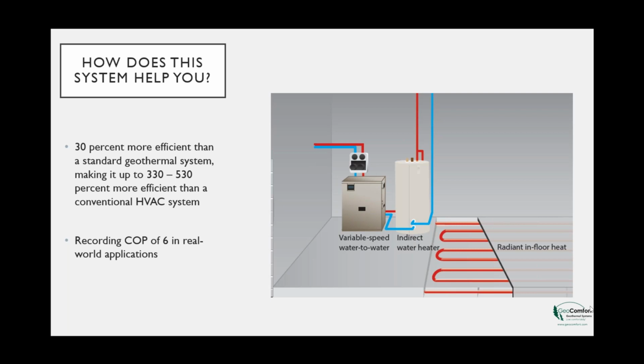So with radiant floor heat, which is already an extremely comfortable system, now we're providing an even more comfortable setup because we're adjusting that water temperature, and we're doing that based on the needs of the dwelling, and of course based on outdoor temperatures. In real world applications, we've seen COPs of 6 or better with this product. And again, it's because we can slow the compressor down, we can bring the water temperatures down, whereas a traditional water-to-water system is running full speed and it's running at its hottest temperature all the time. This system doesn't do it that way.